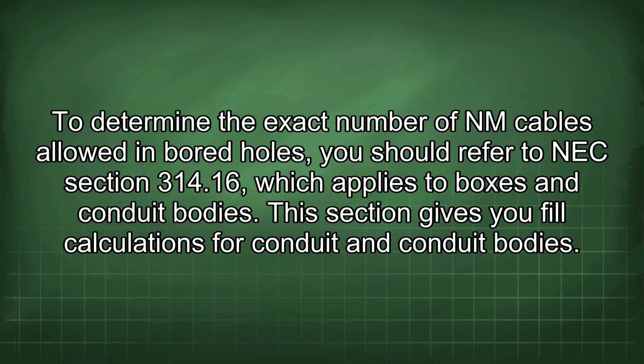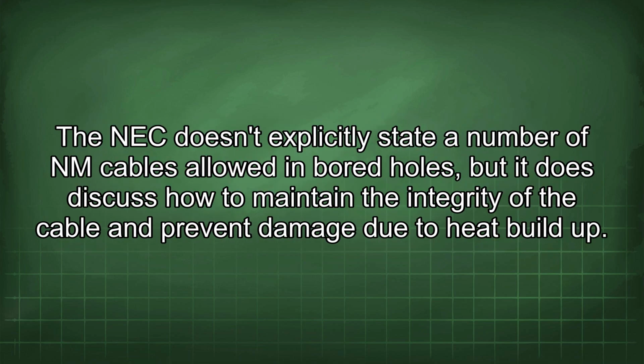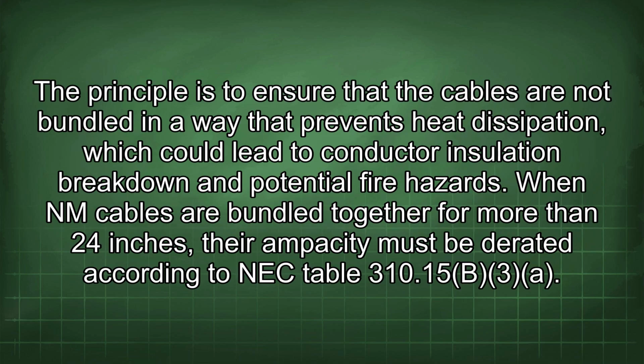NEC Section 314.16, which applies to boxes and conduit bodies. This section gives you fill calculations for conduit and conduit bodies. The NEC doesn't explicitly state a number of NM cables allowed in bored holes, but it does discuss how to maintain the integrity of the cable and prevent damage due to heat buildup. The principle is to ensure that the cables are not bundled in a way that prevents heat dissipation, which could lead to conductor insulation breakdown and potential fire hazards.